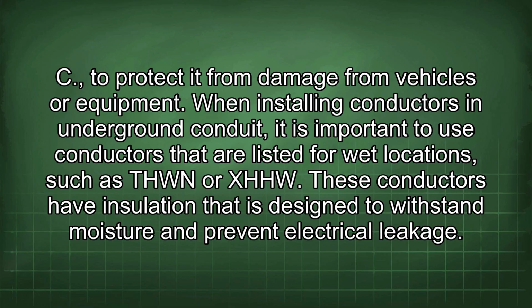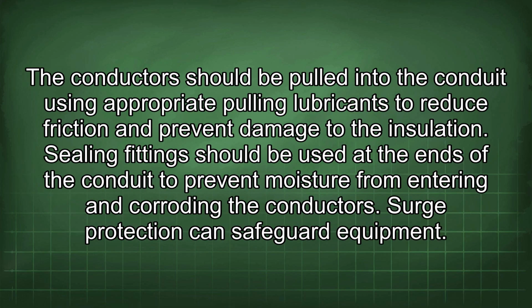When installing conductors in underground conduit, it is important to use conductors that are listed for wet locations such as THWN or XHHW. These conductors have insulation that is designed to withstand moisture and prevent electrical leakage. The conductors should be pulled into the conduit using appropriate pulling lubricants to reduce friction and prevent damage to the insulation. Sealing fittings should be used at the ends of the conduit to prevent moisture from entering and corroding the conductors. Surge protection can safeguard equipment.